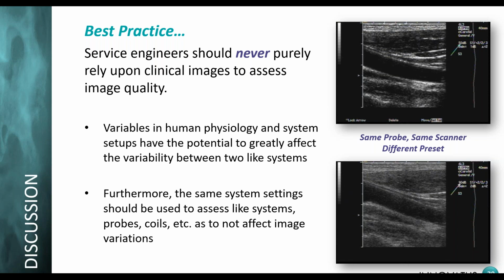No, is it? Okay. So one of the things I did when I was working on ultrasounds is I set up a QA preset within every machine I worked on. And that way, every time I worked on that machine, I'd pull up the same preset, and it was just called QA. And that way, you know you're using the same imaging parameters every single time you touch that machine, for consistency.